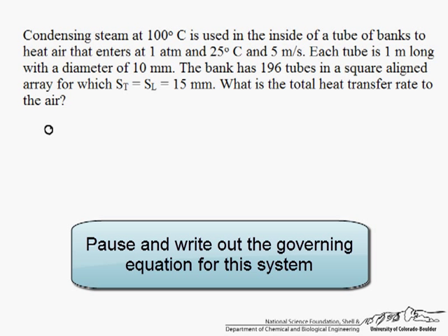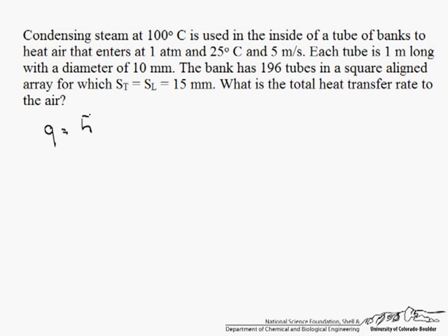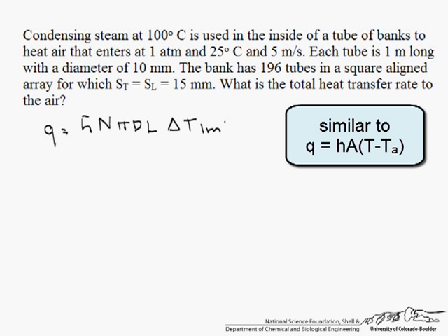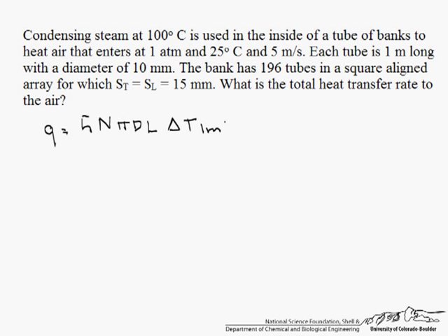So let's start with our governing equation. We're looking for Q, and Q is our heat transfer coefficient times the number of tubes in the tube bank, times the surface area of one of the tubes, times our delta T log mean. The reason we use a log mean temperature rather than just a delta T is because there can be such a difference from the inlet to the outlet.